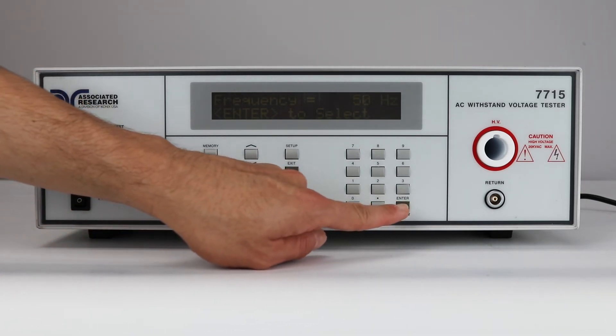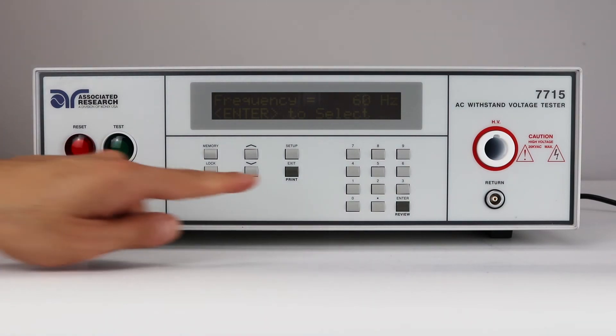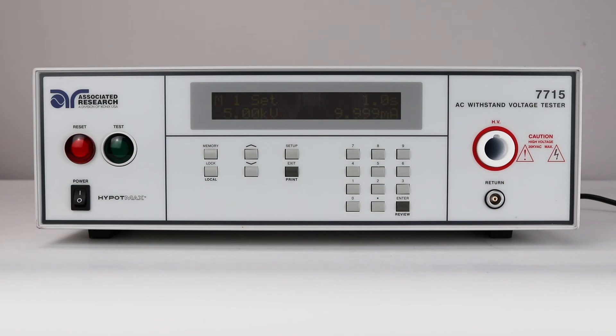For the purposes of this video, the Hypot test will be set to 5000 volts at 60 hertz with a 2 second dwell time. After all the parameters have been adjusted, press the exit key to return to the perform test screen.